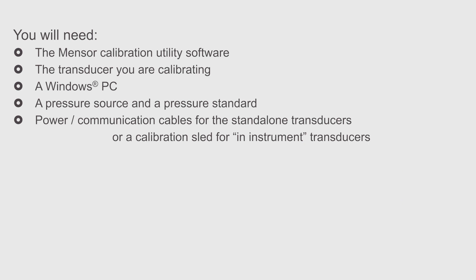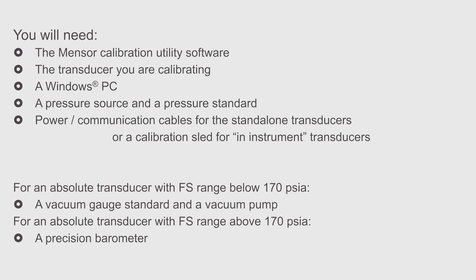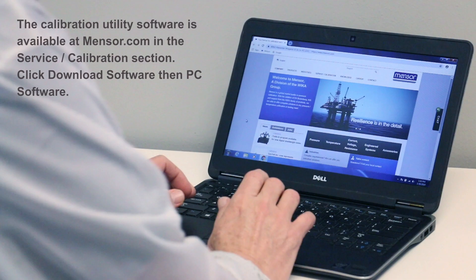For absolute transducers below 170 PSIA, a vacuum gauge standard and a vacuum pump will be necessary. For an absolute transducer above 170 PSIA, a precision barometer will be needed.